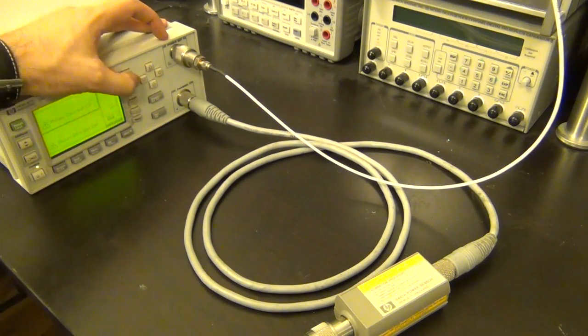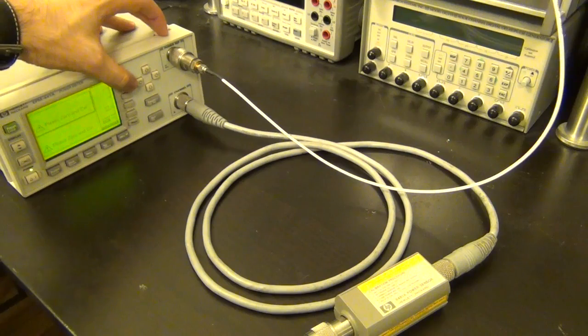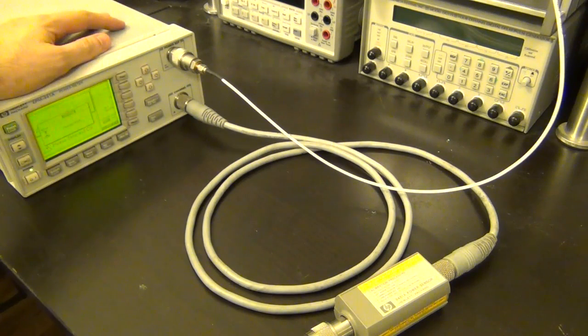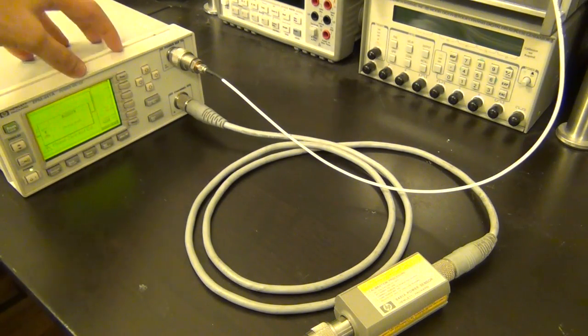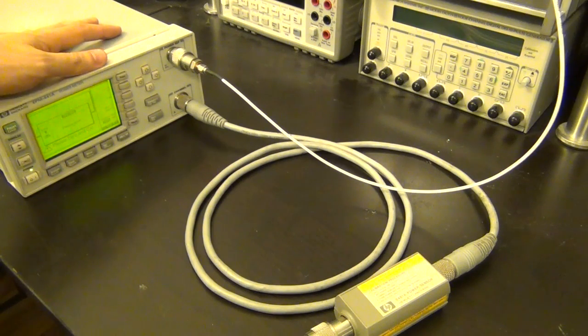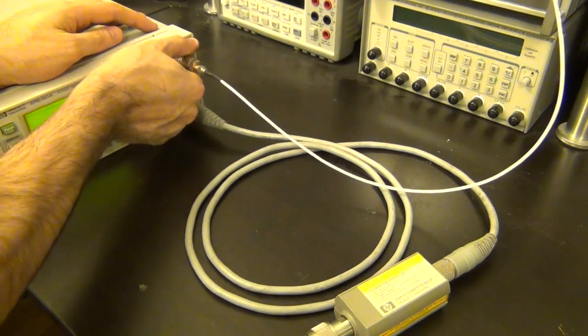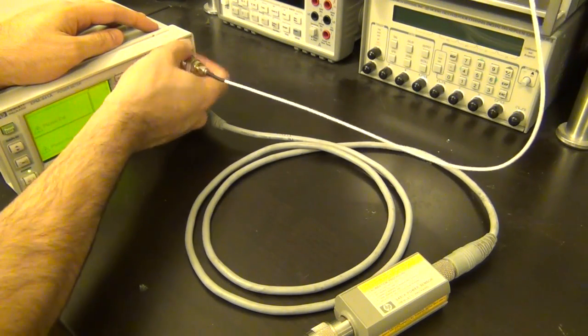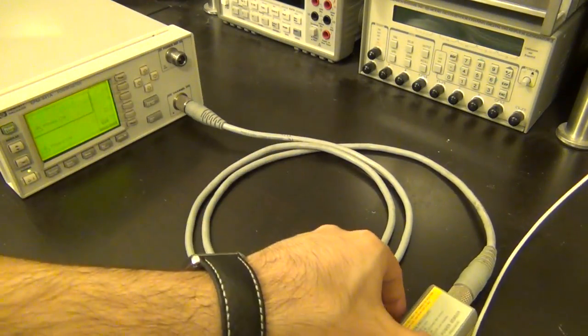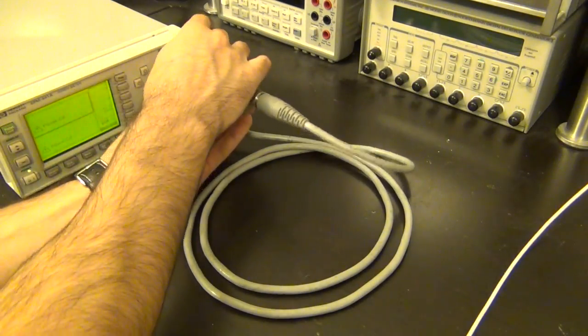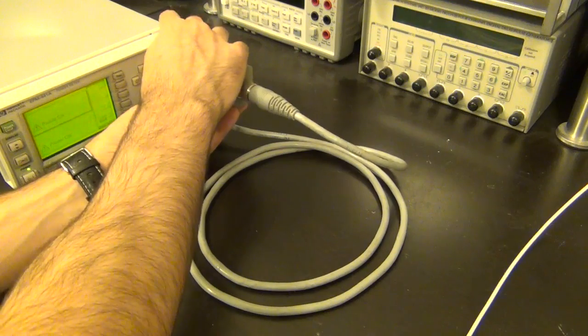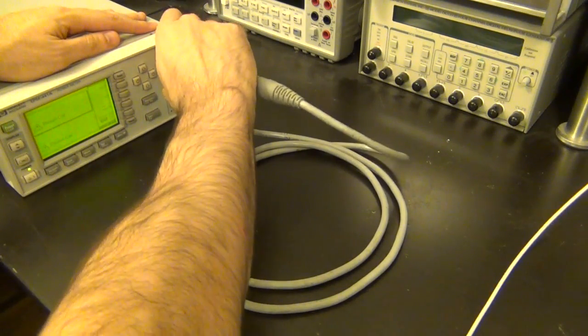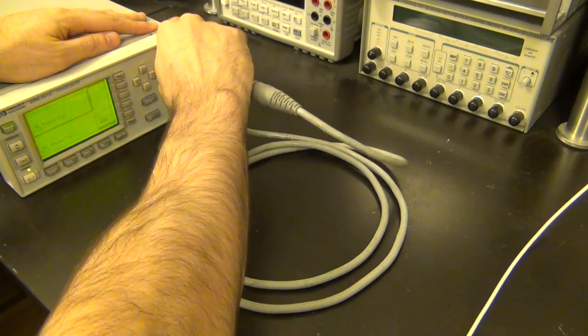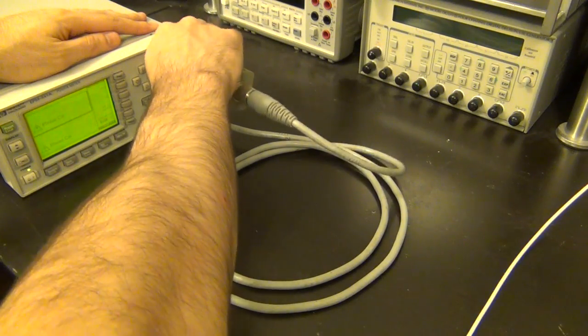I can do that. Here's a 0. There you go. It's zeroing it. It must be set to force you to calibrate and zero. I'm going to change that. That's pretty annoying. So there you go, I just zeroed it and now it says please cal it. Alright, we'll cal it. So I have to take this off now. Let's go ahead and connect this guy in. Anyway, at least this way we can verify that it does the calibration. Even though it may be wrong, at least it will go through the procedure.